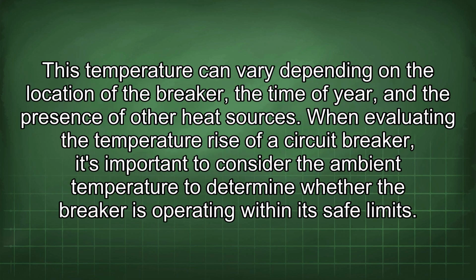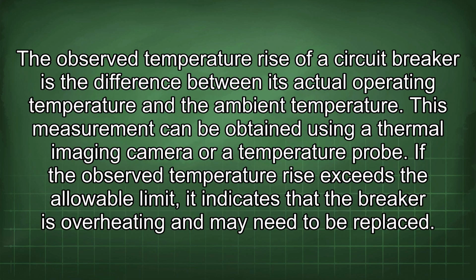This temperature can vary depending on the location of the breaker, the time of year, and the presence of other heat sources. When evaluating the temperature rise of a circuit breaker, it's important to consider the ambient temperature to determine whether the breaker is operating within its safe limits. The observed temperature rise of a circuit breaker is the difference between its actual operating temperature and the ambient temperature. This measurement can be obtained using a thermal imaging camera or a temperature probe.